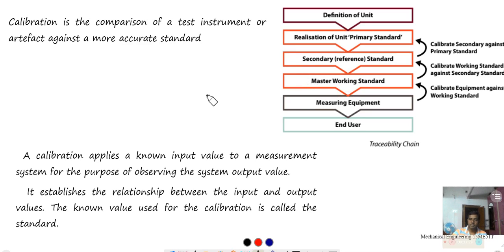That is, a working standard is compared with the second master working standard. So this is the measuring equipment we are going to use on the shop floor. Here, shop floor equipment is compared with the lab working standard. The lab working standard is compared with the secondary working standard, and the secondary working standard is compared with the primary working standard. So by comparing these, if there is any mismatch between the primary standard and the secondary standard, the secondary standard and the master working standard, and the master working standard and the measuring working standard, and that is calibrated by you by adjustments, by inputting some other values, all those things are done, it is called what? Calibration.